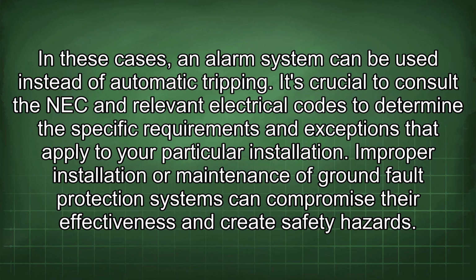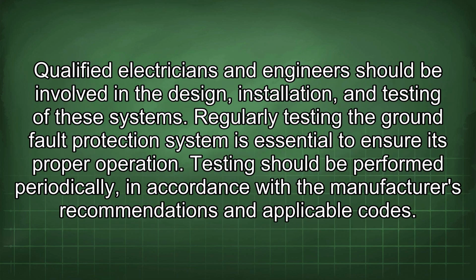It's crucial to consult the NEC and relevant electrical codes to determine the specific requirements and exceptions that apply to your particular installation. Improper installation or maintenance of ground fault protection systems can compromise their effectiveness and create safety hazards. Qualified electricians and engineers should be involved in the design, installation, and testing of these systems. Regularly testing the ground fault protection system is essential to ensure its proper operation. Testing should be performed periodically in accordance with the manufacturer's recommendations and applicable codes.